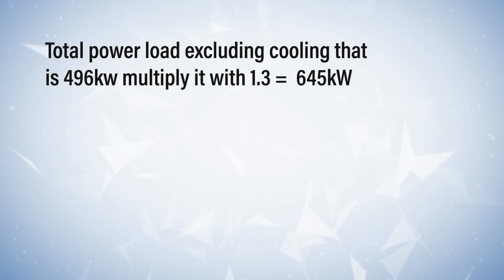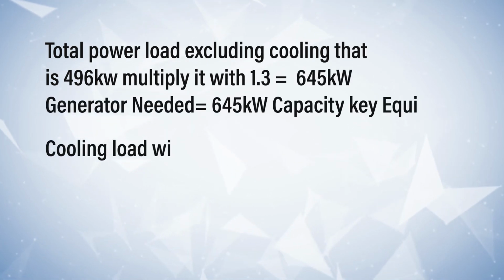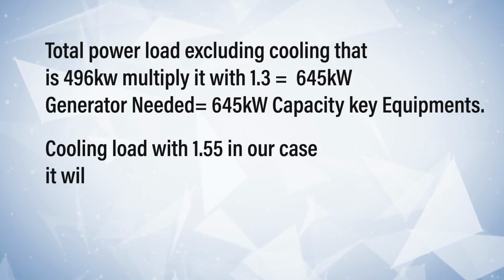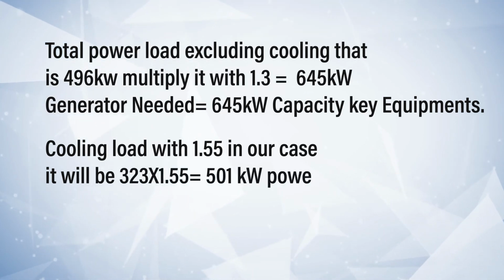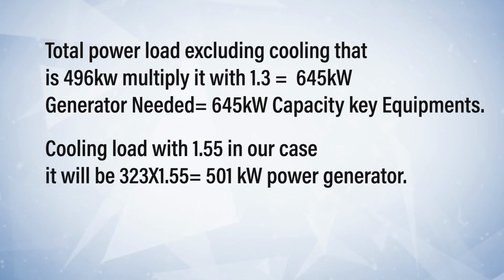Well, congratulations on your perfect calculation, but wait, there is a last step also. For any data center to run completely without downtime, there needs to be a standby generator, because what if there is a power outage? Therefore, you need to calculate the power to know how big a generator you need. Don't worry, it is very simple. Here, the generator is needed for different stages: first for critical load and the second for cooling. Because if you have a low density data center, you can choose not to use generator power for cooling. So, for generator required for total power load excluding cooling, that is 496 kilowatt, multiply it with 1.3, which is equal to 645 kilowatt. So we would need a generator with capacity of 645 kilowatt for key equipments. Now if you need it for cooling also, multiply your cooling load by 1.55. In our case it will be 323 multiplied by 1.55, which is 501 kilowatt power generation.